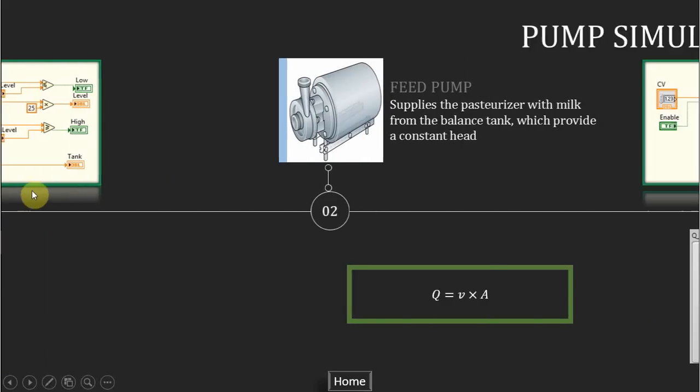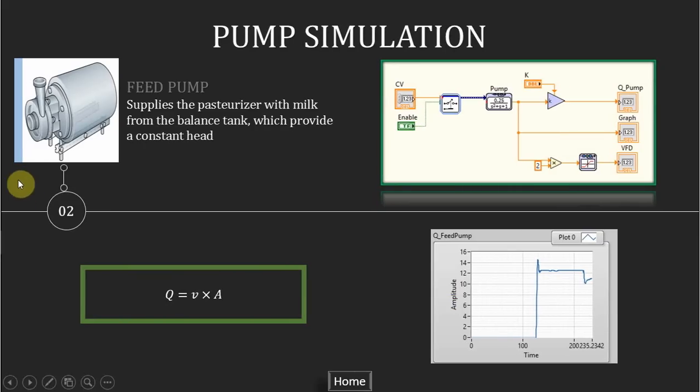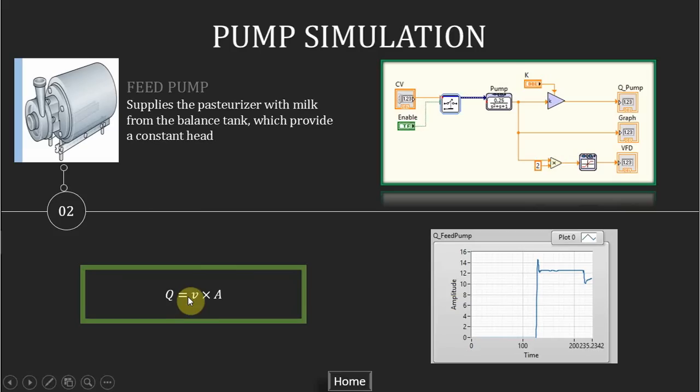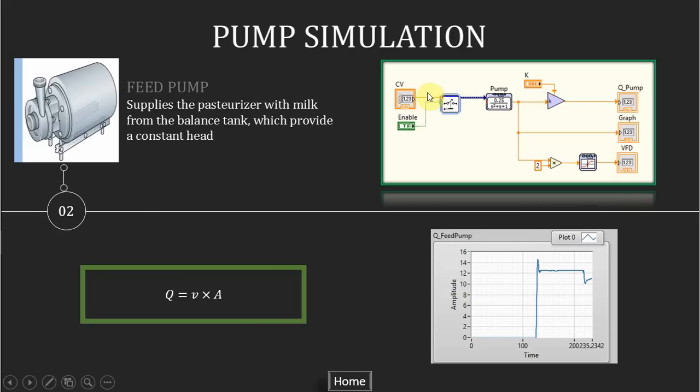For the pump, which controls a process value, the output of the PID controller in the PLC is an analog signal we will transfer to the variable frequency drive, the VFD, to control the speed of the pump. The speed of the pump will affect the flow rate in the pipe by this equation: Q, the flow rate, is equal to the velocity times the cross area of the pipe. I assume that this second order transfer function is for the pump, and the CV, control variable, is the output of the PID from the PLC in the range from 0 to 50 Hz, which will change the flow rate from 0 to maximum 12.5 m3 per hour.